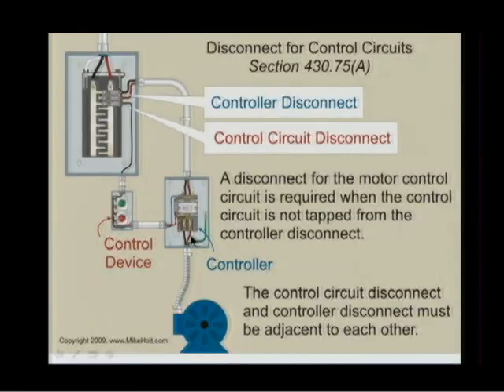All right. But if you ran larger conductors, and if we went with this scenario where you have separate overcurrent protection for the control circuit, then you'd go to table 310.16. Now, for you, Dan, that's pretty common because you're using PLCs, running separate protection, and you get them down to 2 amperes running 16 gauge wire. Eric, you're not having separate overcurrent protection. Let's go to the second one.